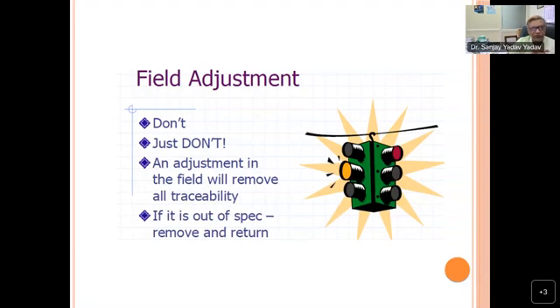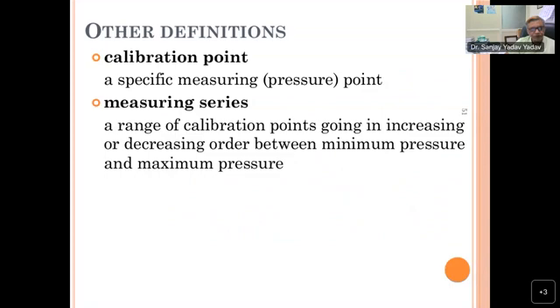So field adjustment is not allowed until and unless there is some regulatory requirement. After the adjustment, you have to have your equipment calibrated. After all this, we need a calibration point and then a measuring series. Suppose for a pressure dial gauge, you have to divide its scale into 10 pressure points. Increasing and decreasing is the measurement cycle.